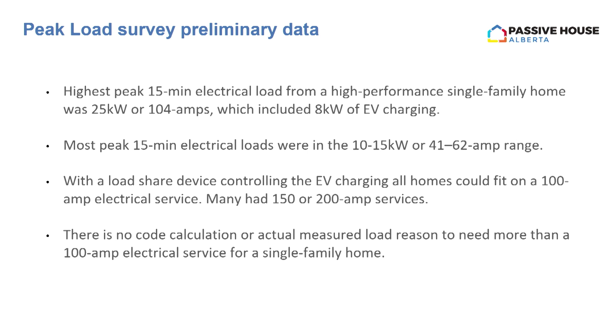So from both the theoretical calculation and the actual data, we should be able to stay on 100 amp service if we're using that EV circuit pauser to control the EV or any other large load that might happen at the same time. So there is no code reason why we can't stay on 100 amp service from the calculation, and what we're seeing from the data is there's no actual measured reason why we can't stay on 100 amp service. So hopefully we can try to do that and not have to double our electrical grid size. That's it.